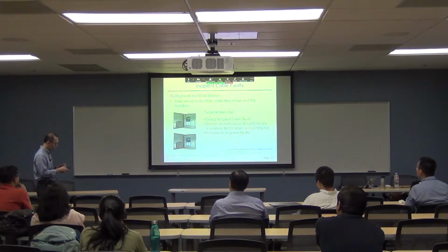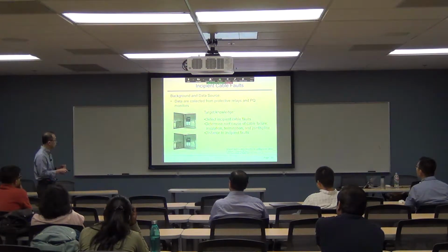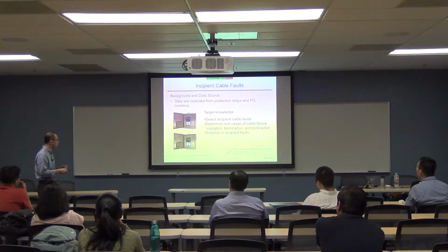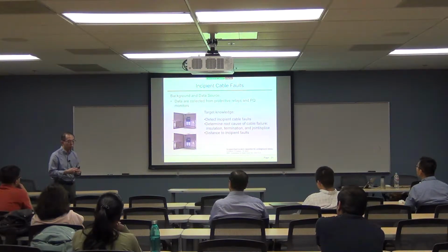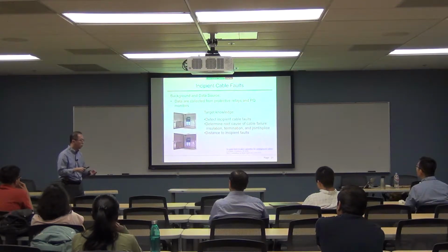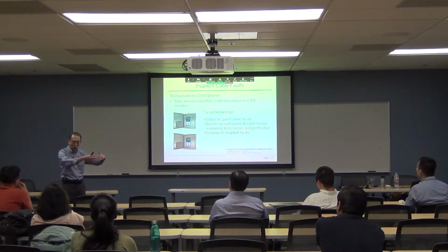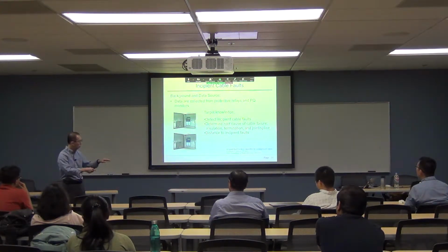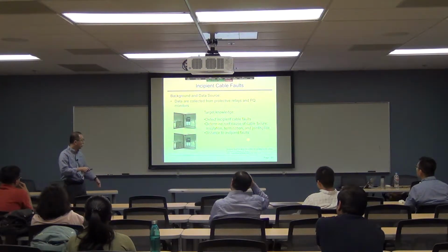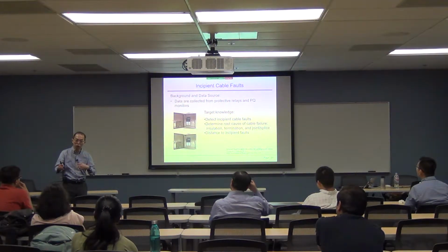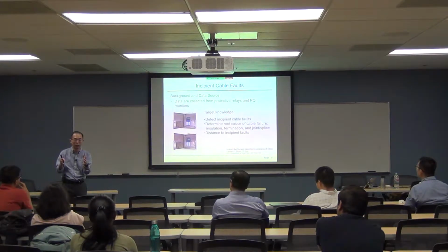There are many things we'd like to find out: first, to detect incipient faults, and then determine the root cause of the cable failure — whether it's on the insulation along the cable body, or at the termination, joint, or splice.